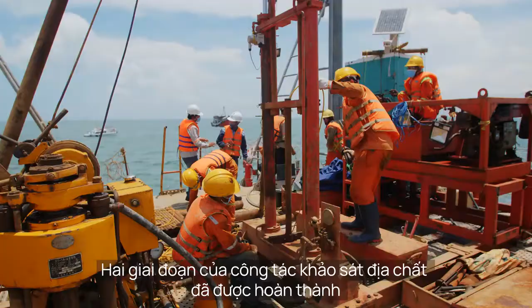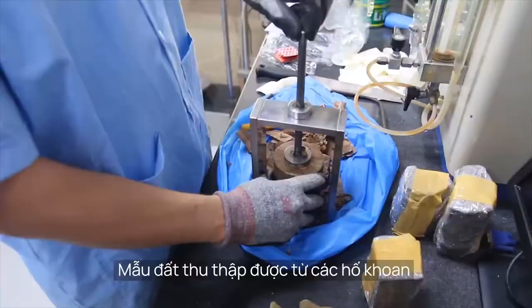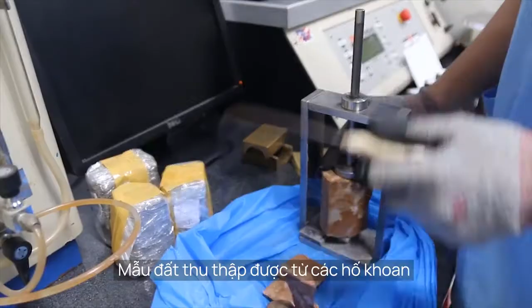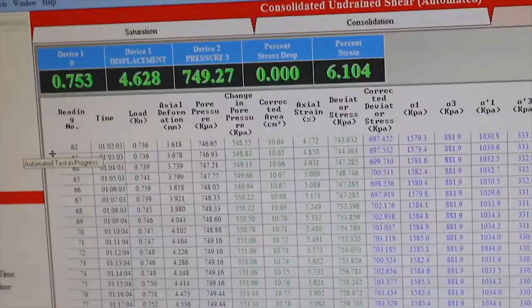Geotechnical investigation is a key development task that examines the subsurface ground conditions at the project site. Two stages of geotechnical investigation have been completed. The first stage was completed by Fugro, who drilled boreholes to 50 metres depth in the Phase 1A area using a floating barge. The second stage was completed by Technical World in 2020, using a jack-up platform, as seen here. They completed boreholes up to 70 metres depth in the Phase 1B area and also completed cone penetration tests. The soil samples recovered from the boreholes have been tested at local company Technical World Laboratory in Ho Chi Minh City, and these test results are used in the design of the wind turbine foundations.